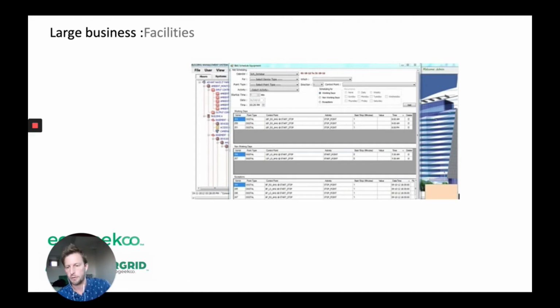Now we're on to large facilities. So this is for people who have buildings that might have lots of HVAC equipment or what's called building management systems. So if you have a building management system, right now your best friend is your scheduler. So if you're able to open up your scheduler on the BMS or talk to your controls engineer, what you want to do is review all the points on that schedule to understand what equipment is programmed to come on and when. And then you can logically go through it and just do a quick risk assessment of going, okay, well, if we switch this off or switch it into holiday mode or program it off for the rest of the next month, what is the possible impact on my facility?